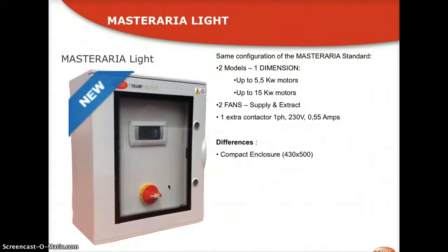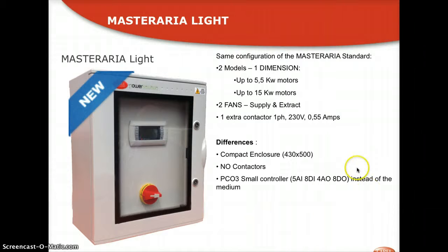The differences are that it has got a compact enclosure compared to the Masteraria Standard, has got no contactors for fans, so you would typically seek power supply for your inverter straight off the circuit breakers. You have a PCO3 small controller instead of a medium, so it's got a slightly less amount of inputs and outputs, however still enough to cover a medium size air handling unit.